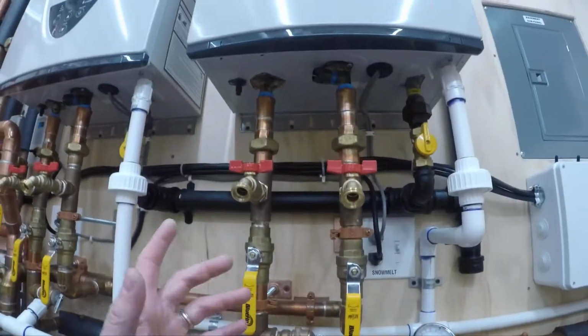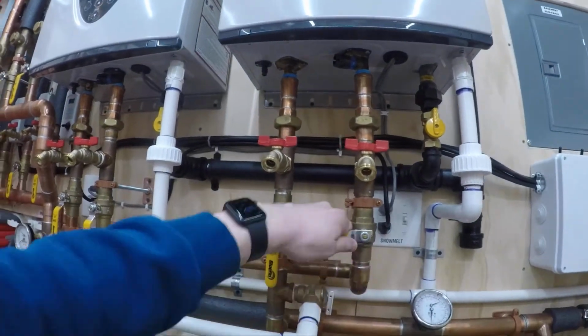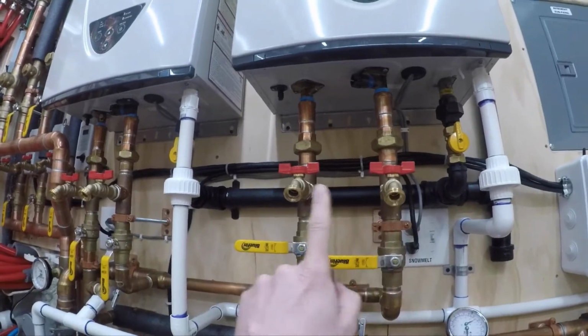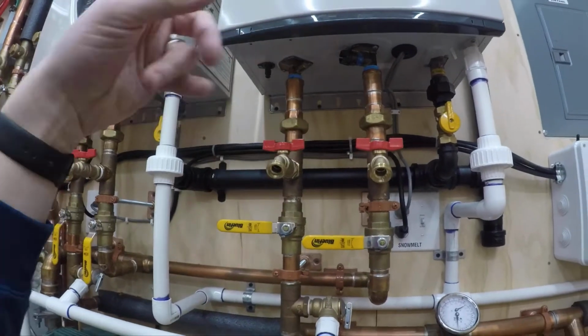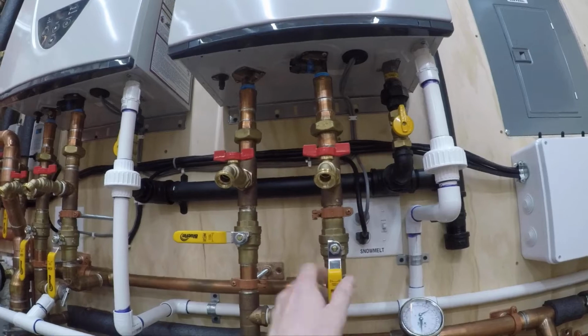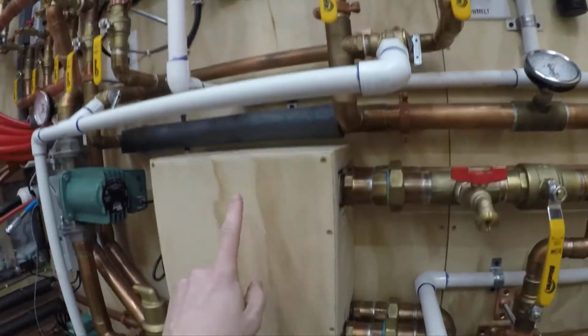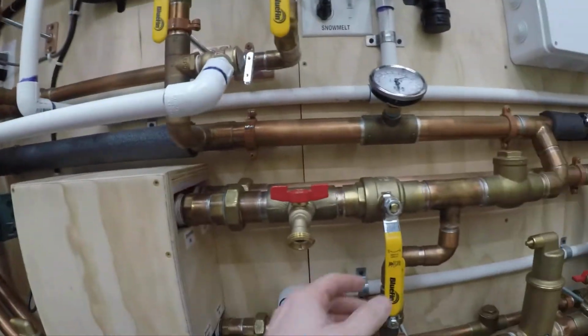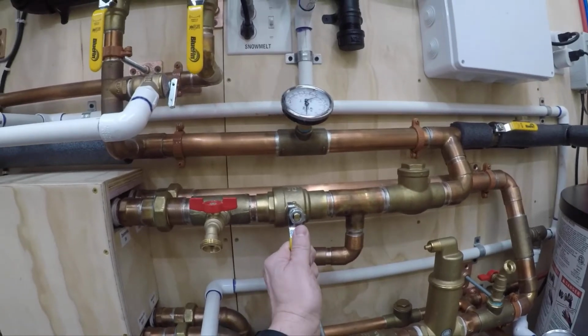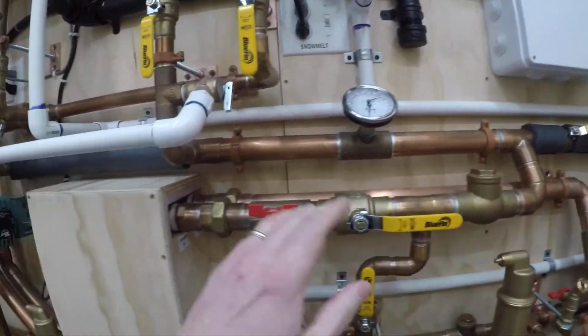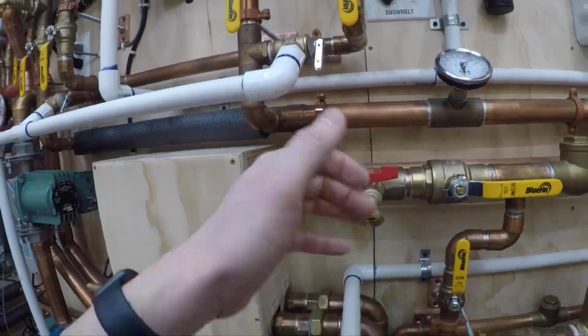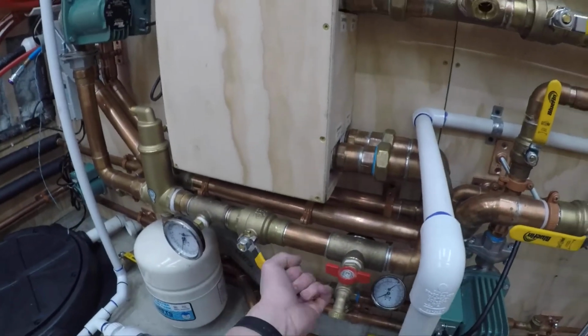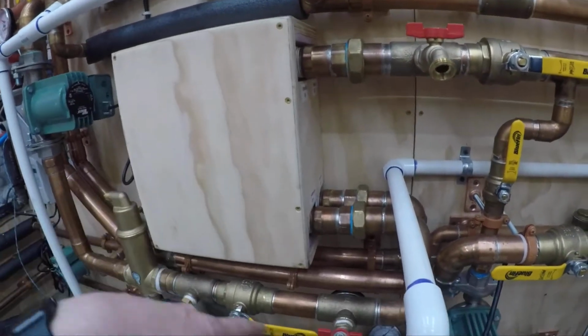Just like once a year, you shut these valves off like this, and you hook up your pump, and you flush these things with vinegar just to keep any buildup or anything out of them. Okay, well, I want to do that on this heat exchanger too. So I designed this with basically a shut-off valve, a drain, same thing down here, so that I can go ahead and flush that out.